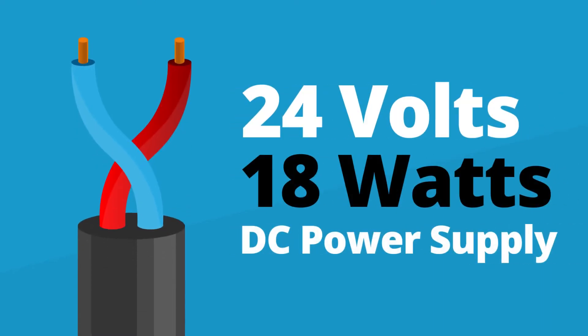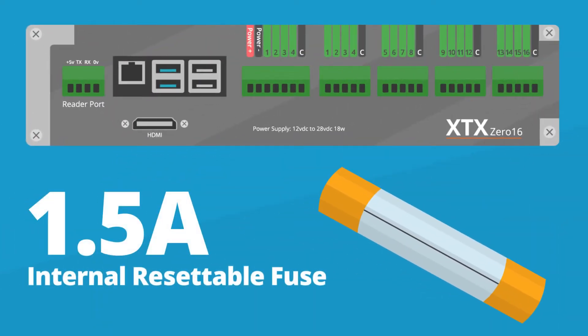A 24 volt, 18 watt DC power supply is needed at the location of each XTX module. Whilst each module is protected by an internal 1.5 amp resettable fuse, an inline fuse should be provided to protect the wiring against over current.